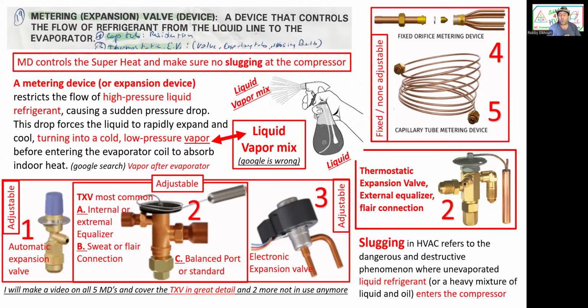Slugging is a very important word in HVAC. It refers to a dangerous and destructive phenomenon where unevaporated liquid refrigerant or a mix of liquid and oil enters the compressor and slugs it, because you cannot compress liquid. Liquid is the strongest thing there is, believe it or not. The Grand Canyon was made by liquid. So what do you think liquid is going to do to the piston of the compressor? I'll cover slugging in more detail when I do the compressor. But now let's move on.